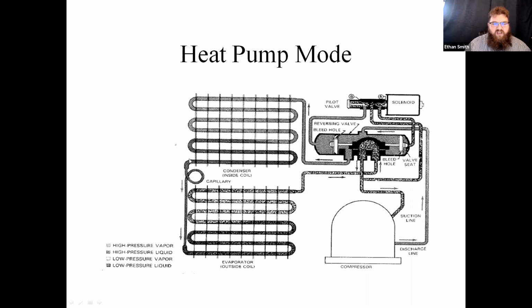So this brings up the point that if you are working on a conventional system, you can't always just gauge up to the line sets in these heat pumps, because your line set in the heating mode is all on the high side of the system. Okay, it's just different sides of the condenser. So in order to get a true pressure reading, you need to make sure that you're gauged up to the true suction line and the true high side of the system. So high side's really easy. You can get it a number of different places. Suction line is almost always going to be that center pipe off the bottom of the reversing valve. And most manufacturers will make provisions for you to get onto that pipe.